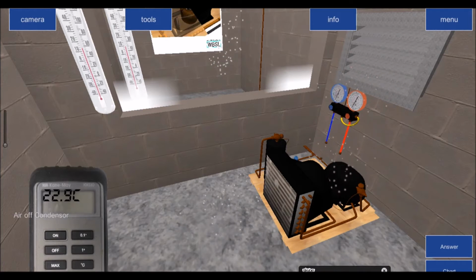It would be in this extract grid here. So the condenser would be outside drawing the air in, and then that air would be channeled back out a vent out the other side. Any air that's drawn across the condenser is going to be hotter, so hot air rising would have to find somewhere to exit. So it might exit a vent beside it, or a vent above it, or a vent on the back wall here, if that back wall was to outside space.